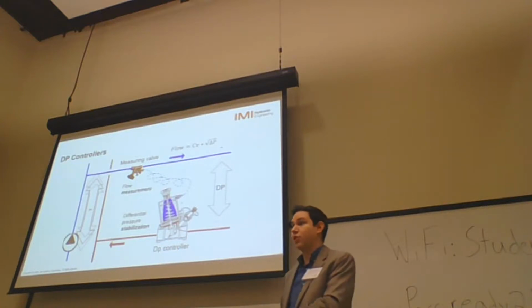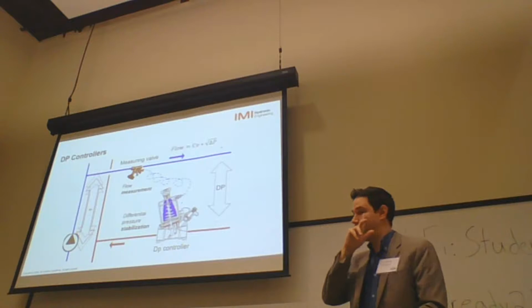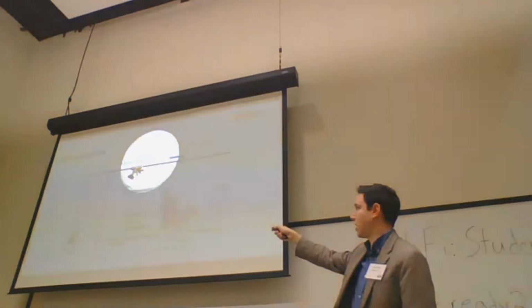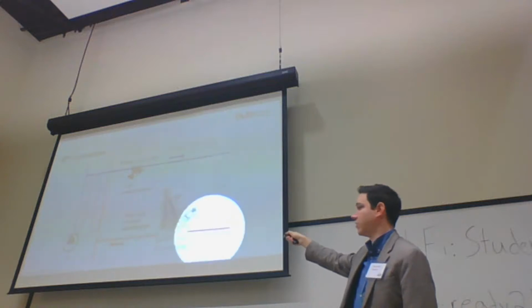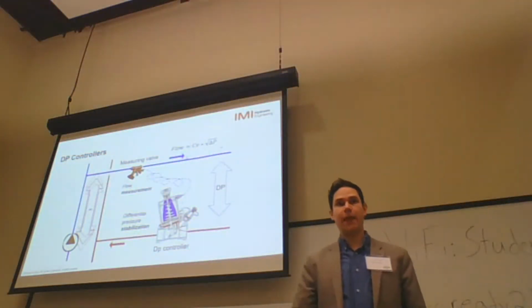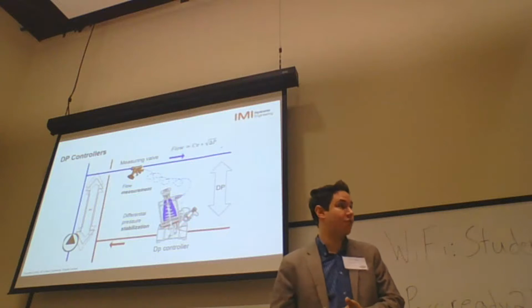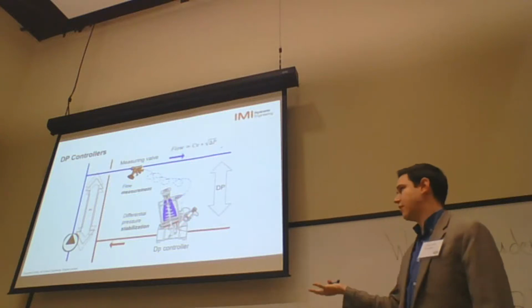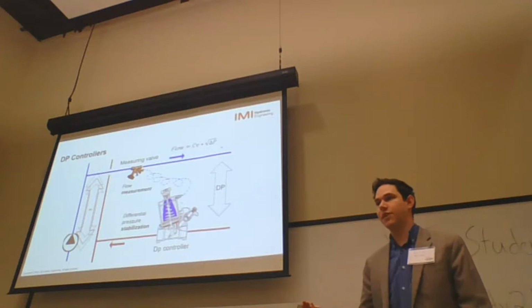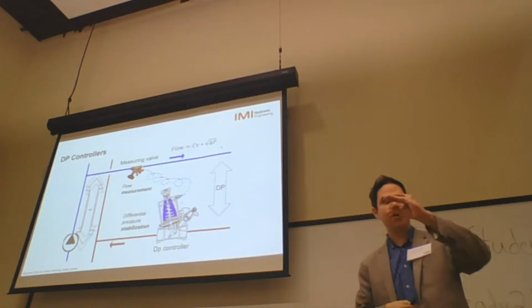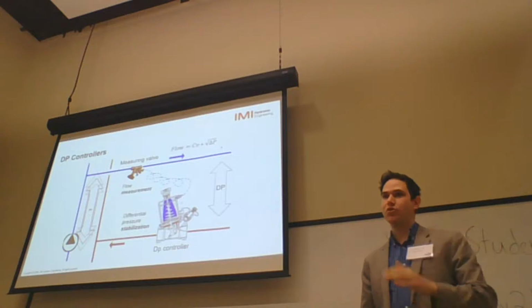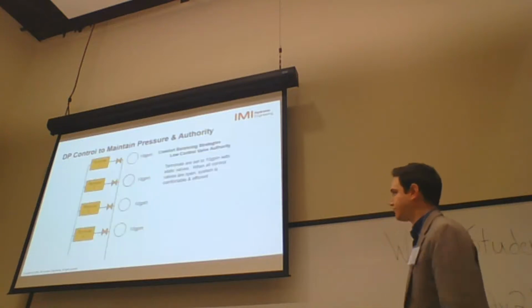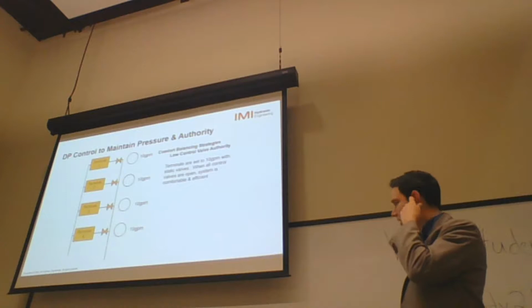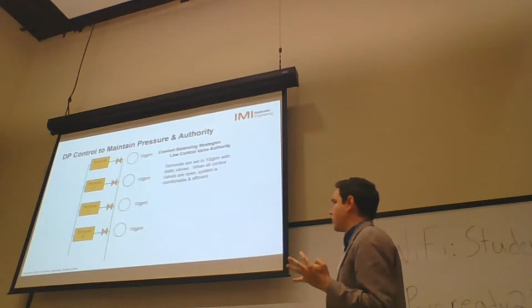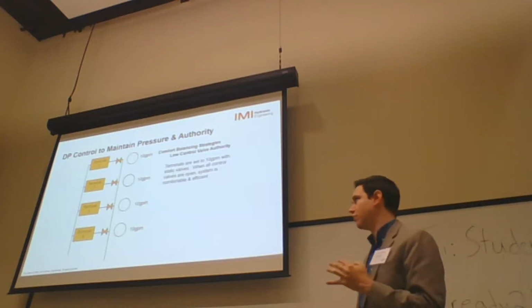Remember that we're always talking about differential pressure, not static pressure. So if the pressure increases on the supply, the DP controller will increase the pressure on the return to keep a stable differential pressure for the branch. And that's how you can keep a stable flow for the installation. The opposite is also valid. If the supply decreases, the DP controller will open on the return to keep the same differential pressure again. So, another simple schematic with only 4 terminal units, 10 GPM in each coil.